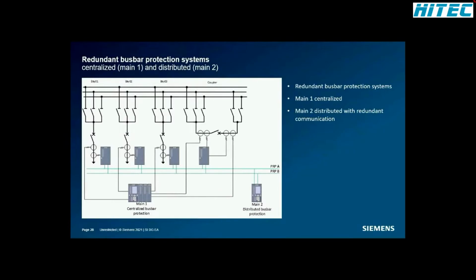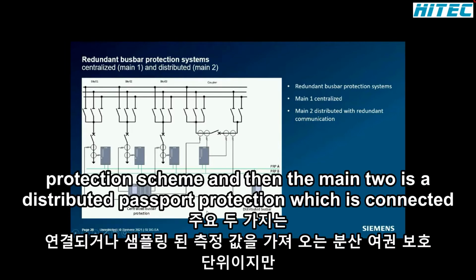Sorry, Adnan. No, I was saying that in this slide, in your example, you are showing a redundancy where the main one is connected directly to the CTs, which is a centralized busbar protection scheme. And then the main two is a distributed busbar protection, which is getting the sampled measured values from the bay units. But we can also modify this slide and put that both main 1 and main 2 are getting the sampled measured values from the same bay units. Is that correct? Yes. Okay, so be careful.